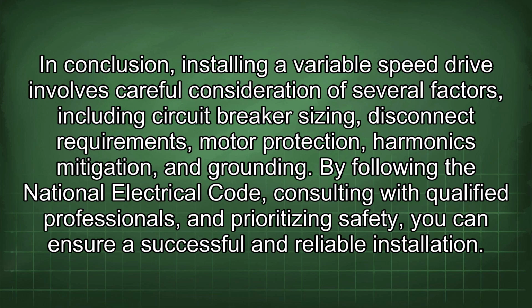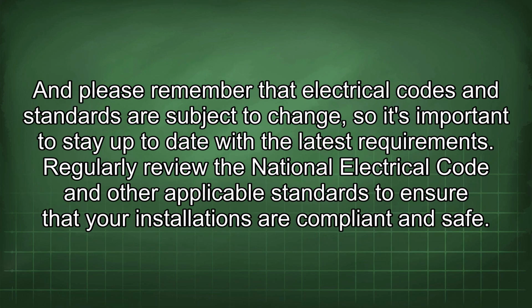In conclusion, installing a variable speed drive involves careful consideration of several factors, including circuit breaker sizing, disconnect requirements, motor protection, harmonics mitigation, and grounding. By following the National Electrical Code, consulting with qualified professionals, and prioritizing safety, you can ensure a successful and reliable installation. And please remember that electrical codes and standards are subject to change, so it's important to stay up to date with the latest requirements. Regularly review the National Electrical Code and other applicable standards to ensure that your installations are compliant and safe.